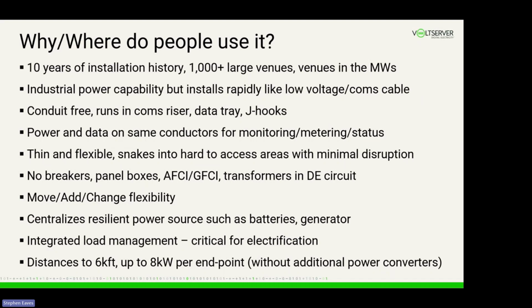Another real core component is integrated load management. As many of us have found out, when converting buildings, electrifying them, and displacing natural gas, that peak power impact means you can't use brute force techniques anymore. You have to manage the loads, and often they can be managed without any effect on the customer or tenant—if you're running the stove at peak power, you don't necessarily need to make as much heat in the apartment, so you can turn down the heat pump.